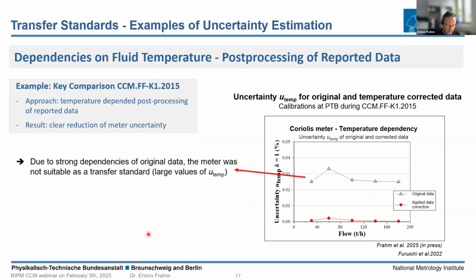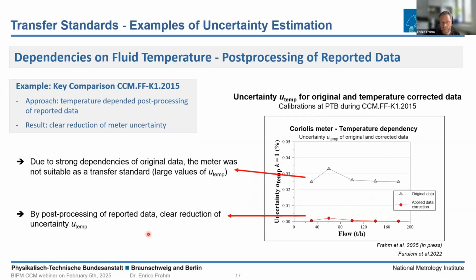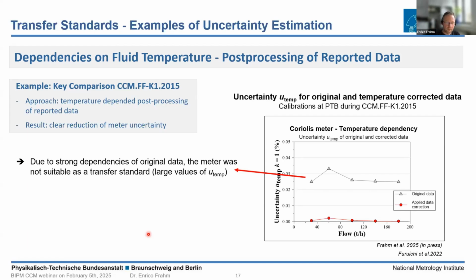So the uncertainty of the meter induced by the original temperature dependencies gives too large uncertainty values. So in this case, the meter was not suitable for use as a transfer standard within this key comparison. So that's why we corrected these temperature dependencies. And by this post-processing of the reported data, you get a clear reduction of uncertainty.